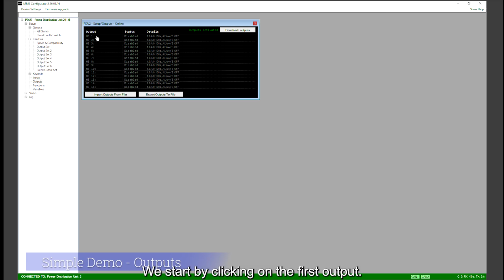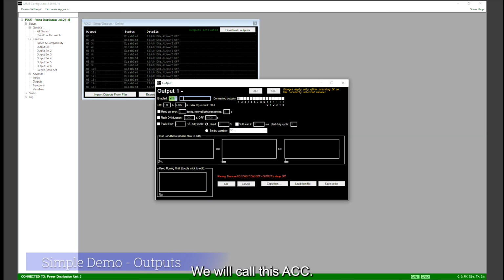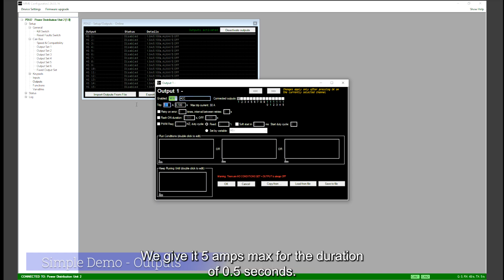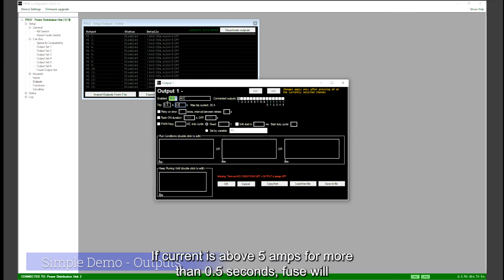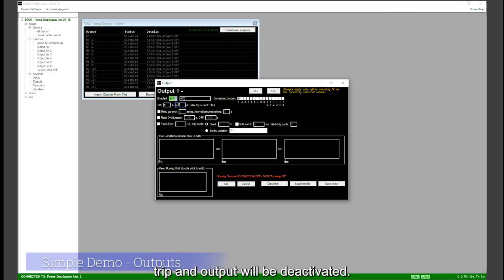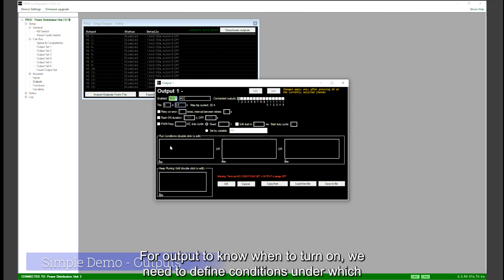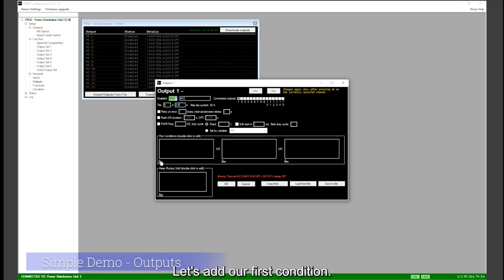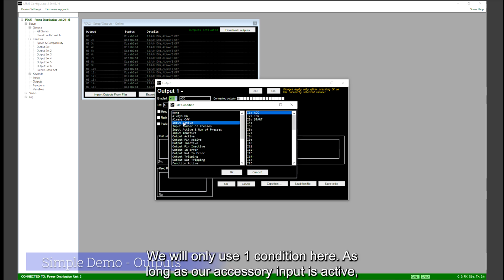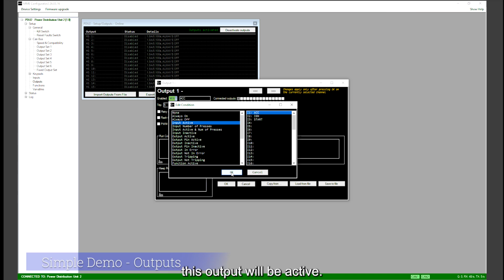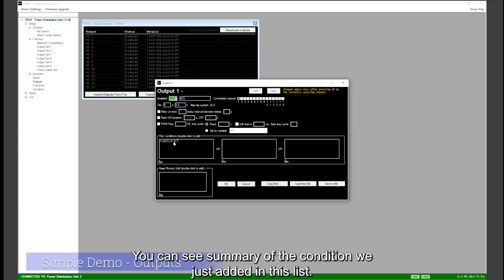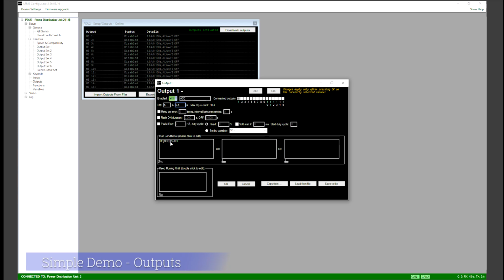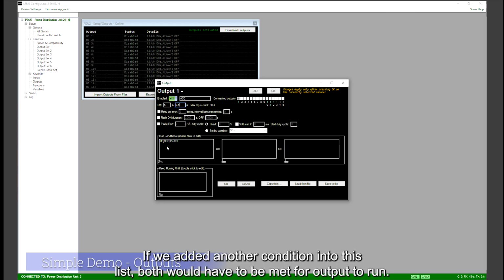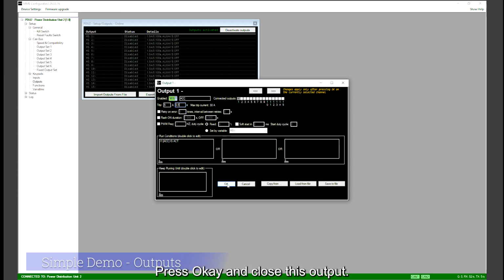We start by clicking on the first output. We will call this ACC. We give it 5 amps max for the duration of 0.5 seconds. If current is above 5 amps for more than 0.5 seconds, the fuse will trip and the output will be deactivated. For the output to know when to turn on, we need to define conditions under which the output is active. Let's add our first condition. We will only use one condition here. As long as our accessory input is active, this output will be active. You can see a summary of the condition we just added in this list. If we added another condition into this list, both would have to be met for the output to run. Press OK and close this output.